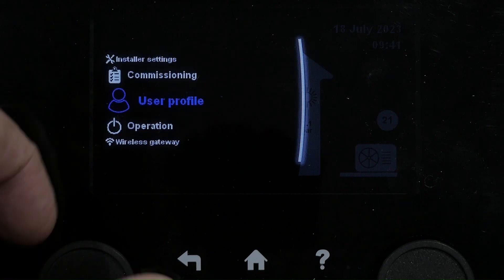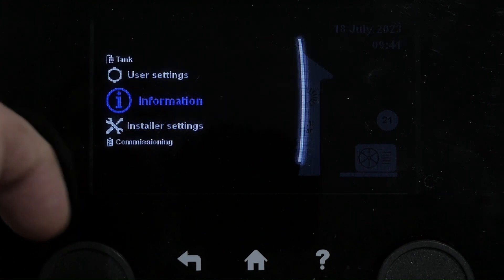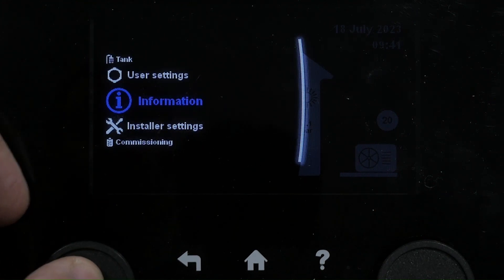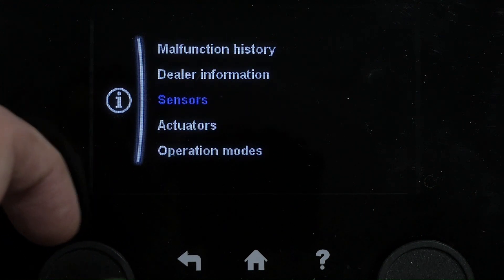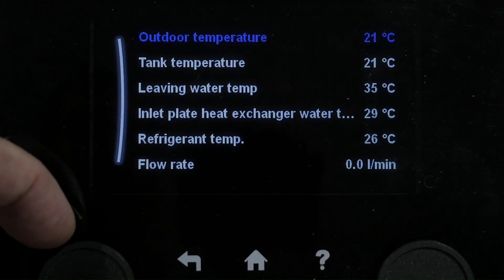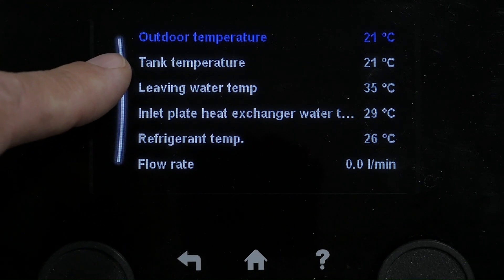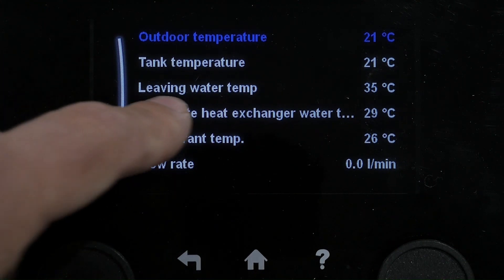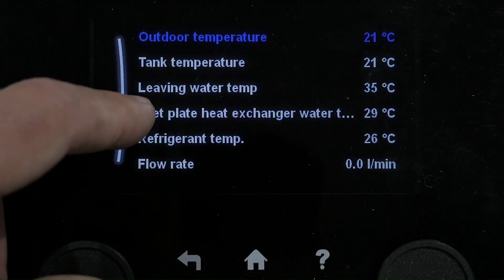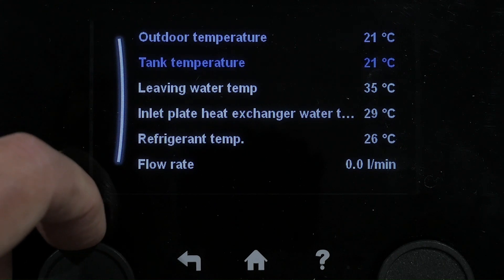If we go to the information screen and go down to sensors, here you'll have your outdoor temperature, tank temperature, leaving water temperature or flow temperature from the unit, and return temperature — so you can see your delta T across the two — and your refrigerant temperature as well.